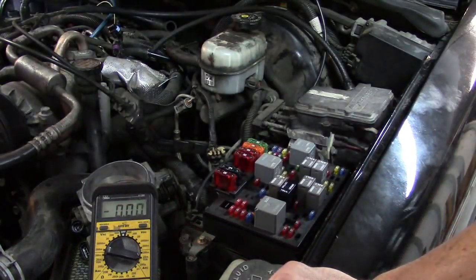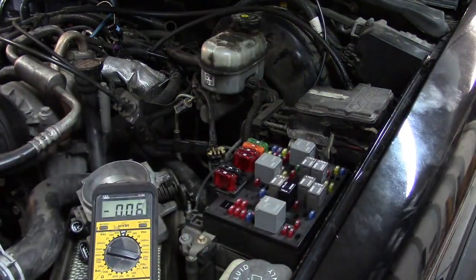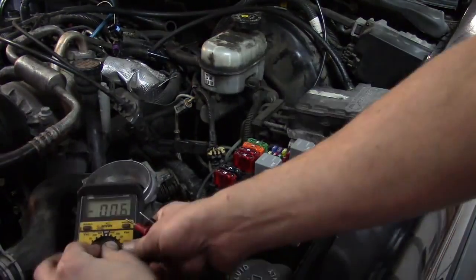I pull the fuse and watch that my low amp probe shows the circuit drops altogether. By doing that method, I still never have to take my meter out of voltage mode.